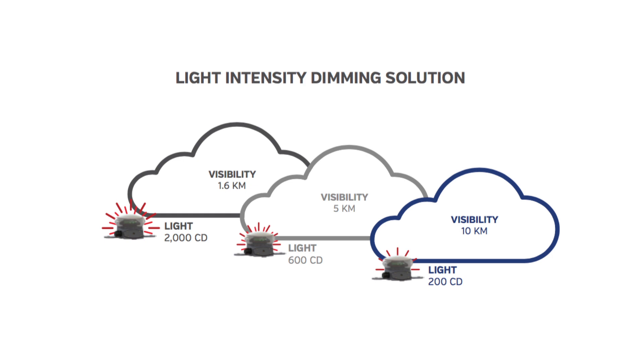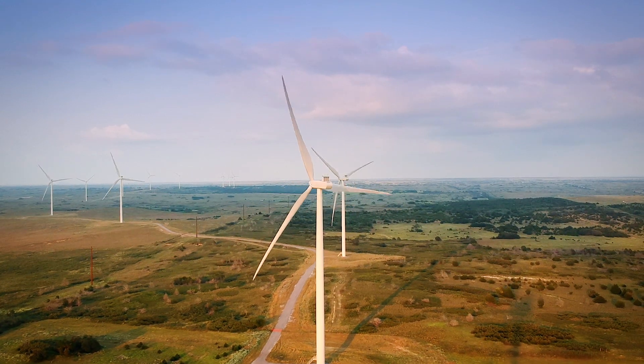The brightness of the lights are increasingly becoming a point of contention between wind farm operators and their surrounding communities. LIDS technology is an innovative solution that adapts the light intensity of the beacons with current weather conditions. As visibility increases, the light's output decreases. Local residents will see a noticeable drop in light intensity while pilots will still be able to safely see the turbines in all VFR conditions.